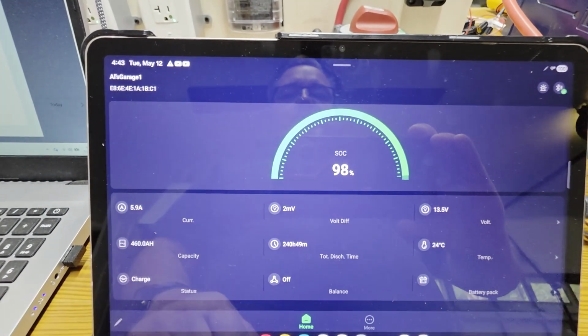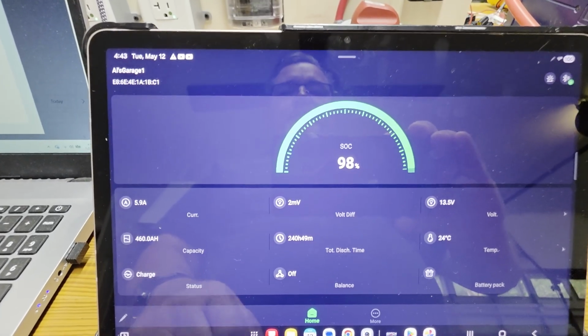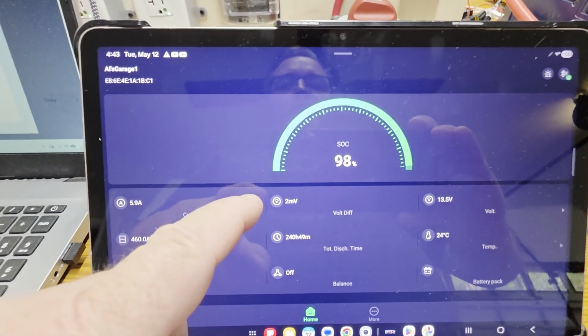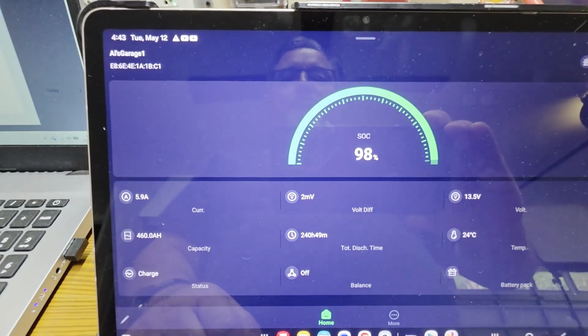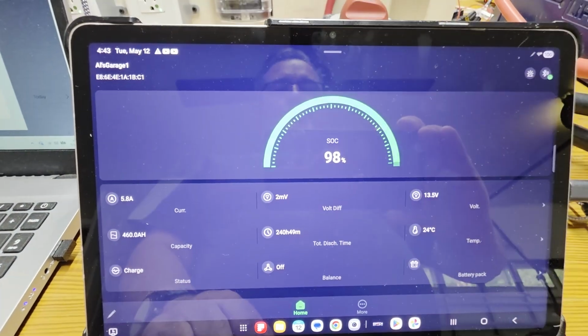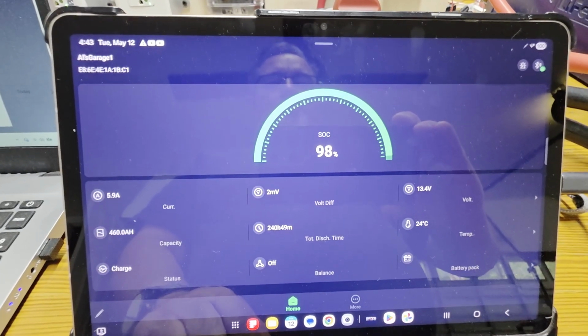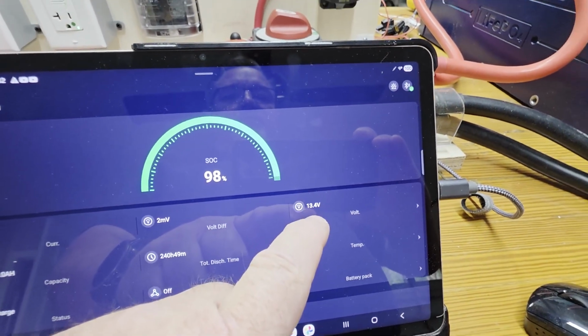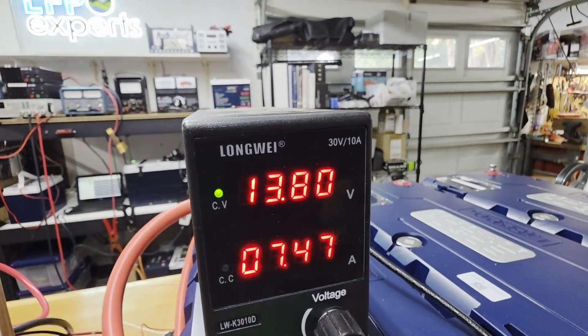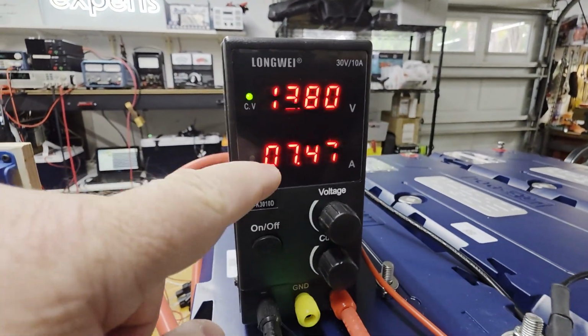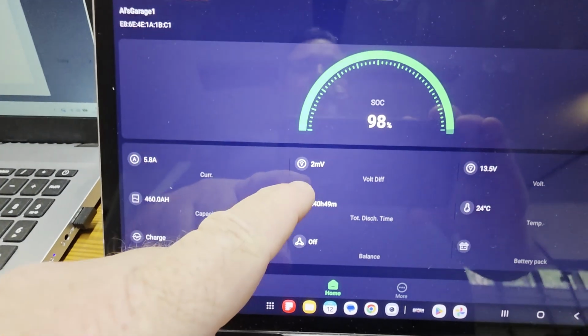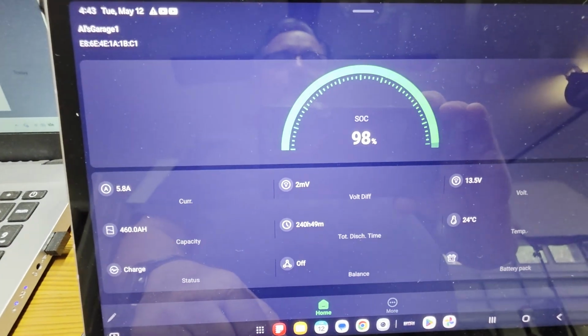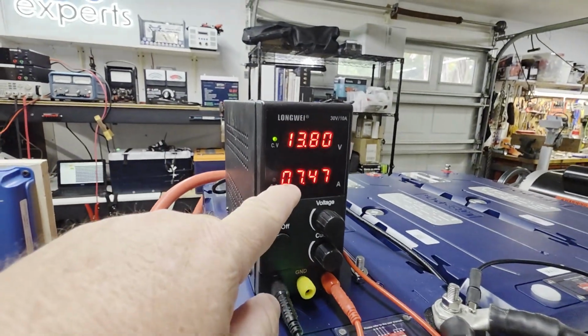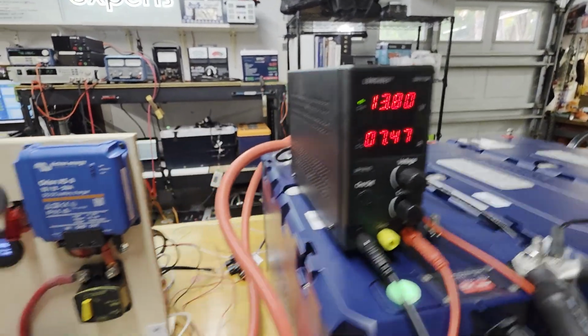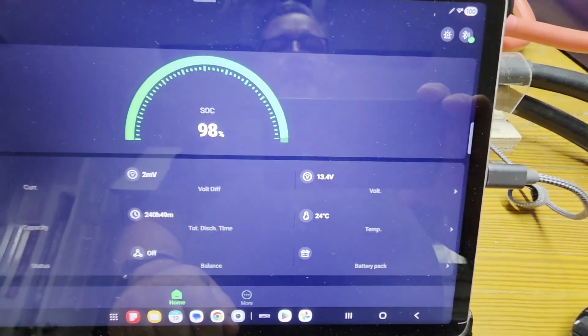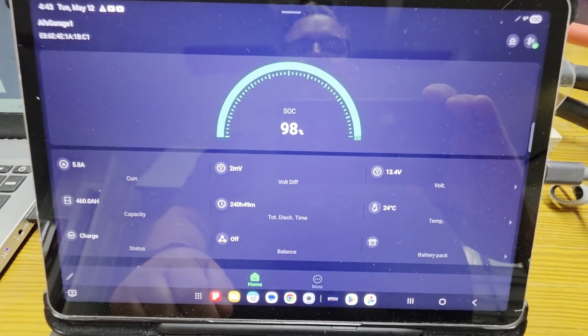In this case it's not going to grow very much because our battery has already been balanced here, but in your case on a brand new battery, when you reach 13.8 here, you might see 100 millivolts, you might see 150 millivolts. We will let this charge up to stabilize to whatever this number is equal to that number here, what you set in there. At that point the current will drop, and whatever this number ends up being when those conditions are set, when this is at almost 0 amps and the voltage of the output and the voltage of the battery are the same, then we're in the conditions for balancing.